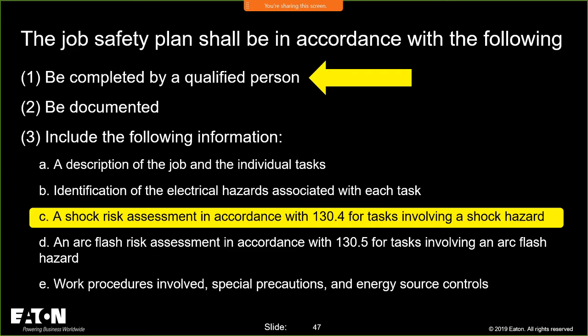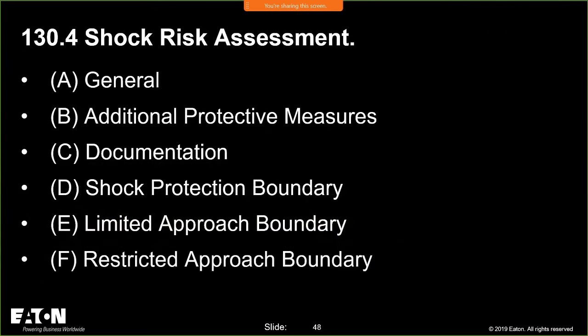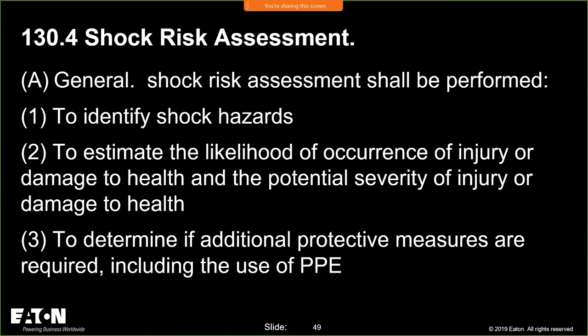The job safety plan, again, involves qualified individuals. You're going to see that word used a lot in 70E, talking about qualified persons. And the shock risk assessment has to be completed with respect to 130.4. The title of that is shock risk assessment. We already talked about it, and we're going to go through that in a little bit of detail, not much. These are the different areas in your shock risk assessment. You have your general requirements. You have any additional protective measures that you need to take, all the documentation. You have to establish your boundaries, your restricted, your limited, your shock boundaries, all of these great things, and your arc flash boundaries, everything. You have to understand who can be in those areas, who can't be in those areas. We should be cording those off to make sure that only the qualified people are in an area that we've designated as one of those boundary areas. You have to identify all your shock hazards.